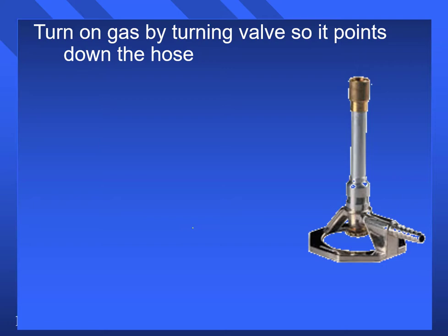What's hooked on underneath that handle is a piece of metal the same shape, same direction. When you spin the handle, it turns pointing down the pipe so that gas can go on either side of it. But when you spin it all the way, it's flat again, and the gas can't go around it. Okay? So we sense how the gate valve works? Okay. So sideways is off.